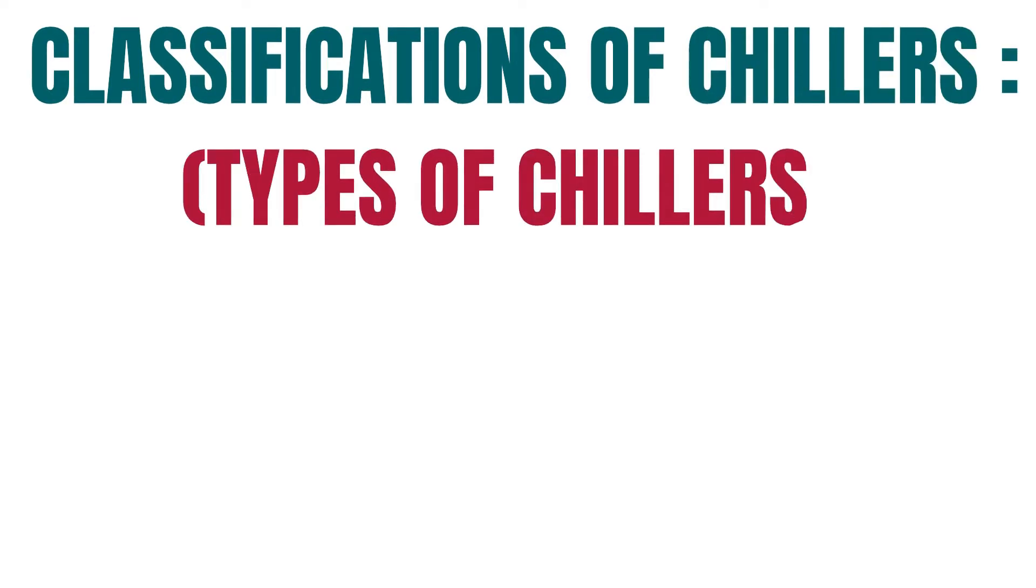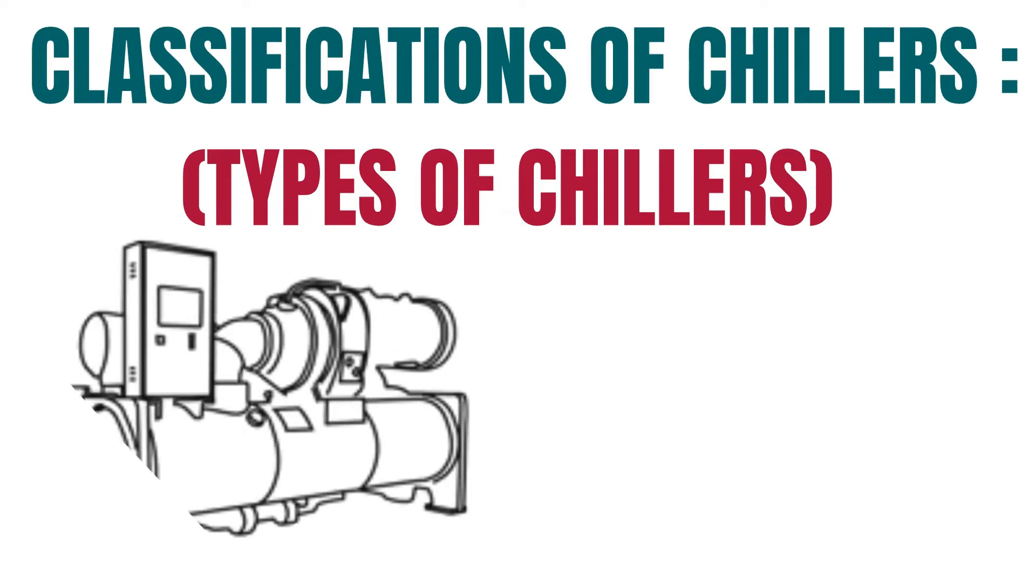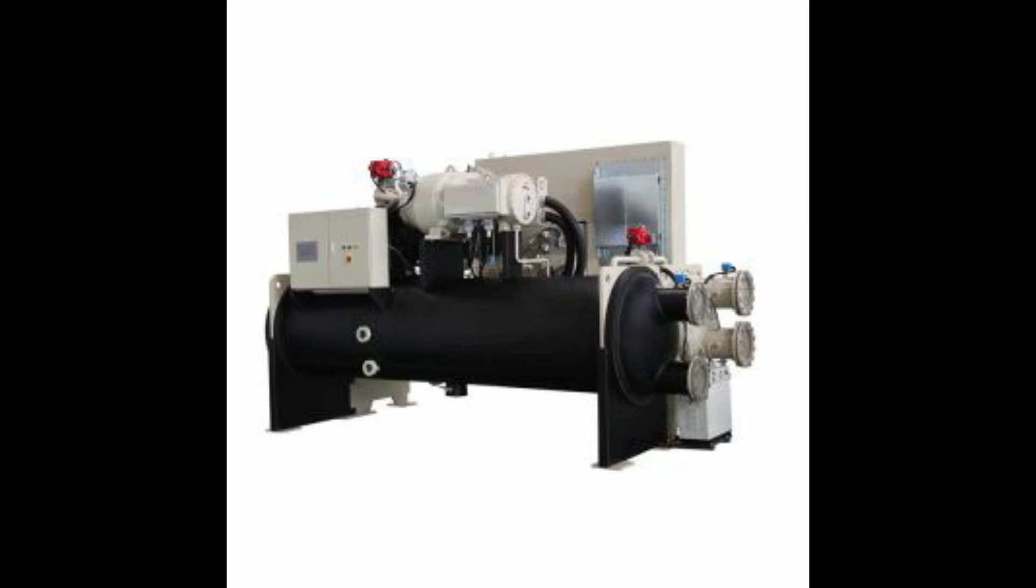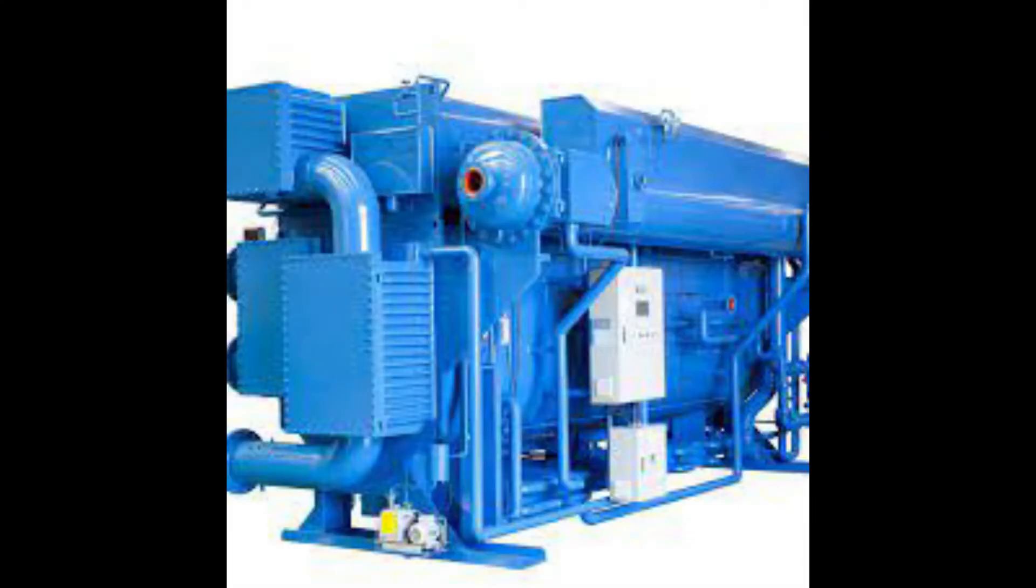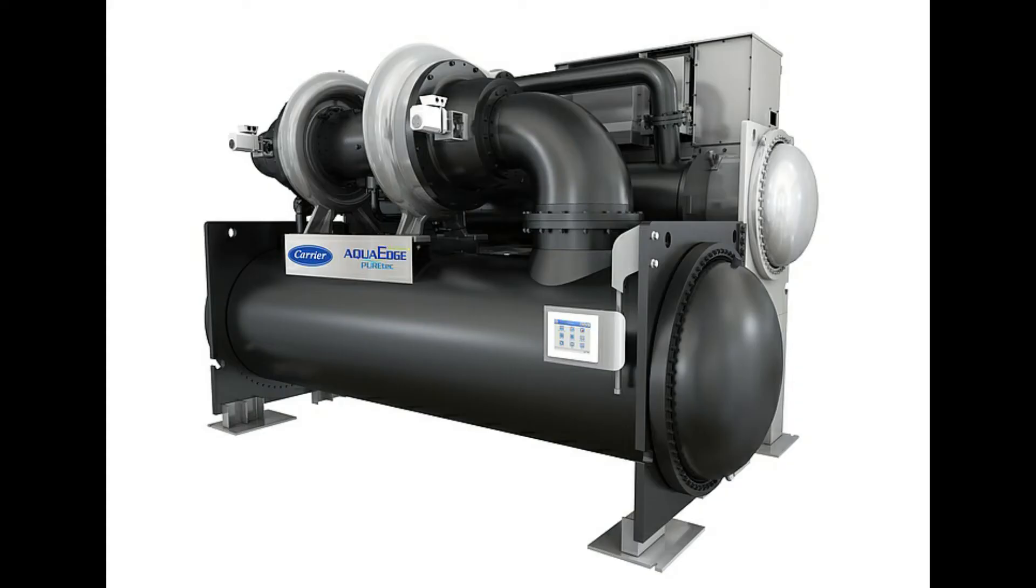Now look into the classifications of chillers in various categories. Chillers fall under two main categories: vapor compression chillers and vapor absorption chillers. Vapor compression chillers use an electrically driven mechanical compressor to force a refrigerant around the system, while vapor absorption chillers use heat energy to move the refrigerant around the system.